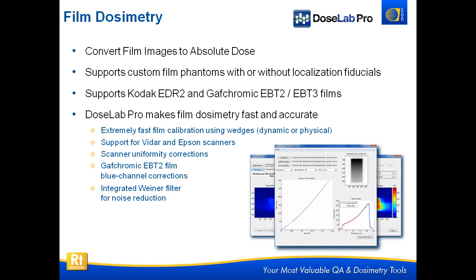Film dosimetry: we have a full film dosimetry package in DoseLab Pro. We convert film images to dose. We support phantoms with or without fiducials. We do Kodak EDR2 film and, of course, Gafchromic EBT2 and 3. Our film calibrations are performed using wedges, either dynamic or physical — it's a very quick and easy calibration method. We support Vidar and Epson scanners, doing uniformity corrections on both: one-dimensional for Vidar, two-dimensional for Epson. We do EBT2 and 3 blue channel corrections, and at the very end we apply a Wiener filter to do a little bit of noise reduction.